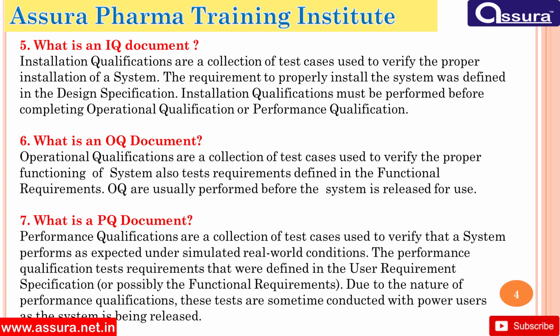What is a PQ document? Performance qualification is a collection of test cases used to verify that a system performs as expected under simulated real-world conditions. The performance qualification test requirements were defined in the user requirement specification or possibly the functional requirements. Due to the nature of performance qualifications, these tests are sometimes conducted with power users as the system is being released.